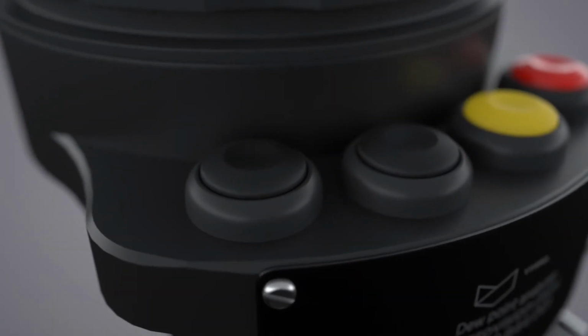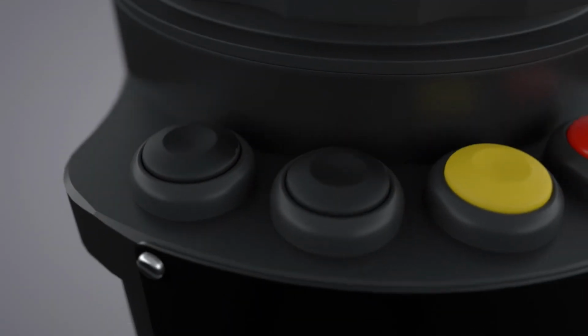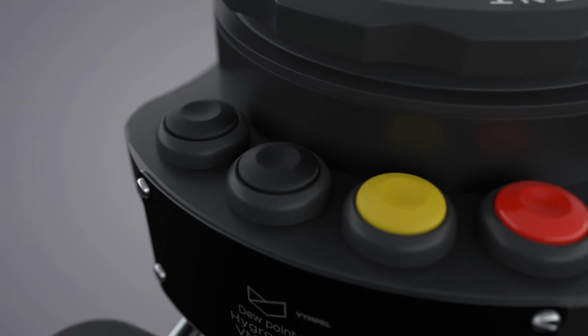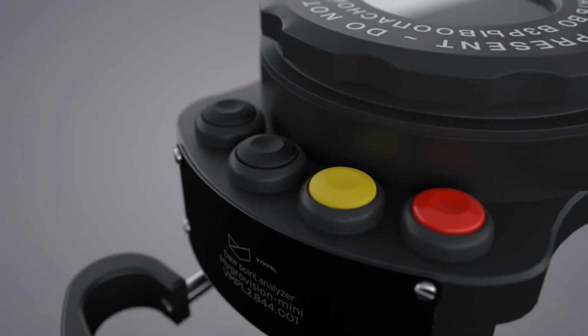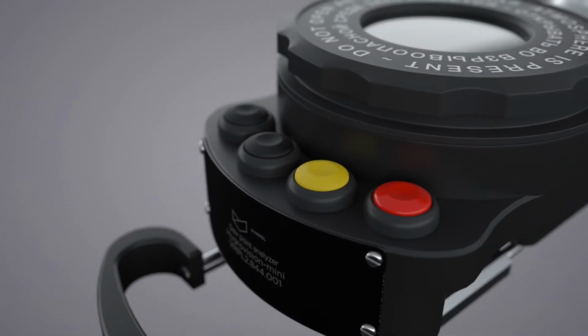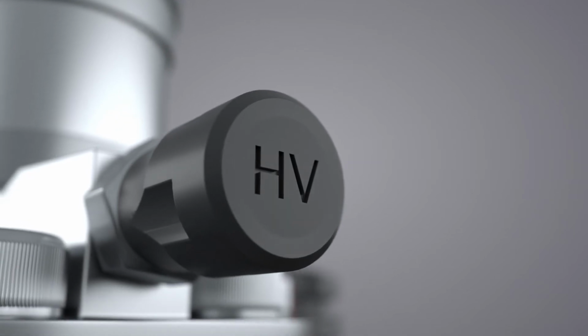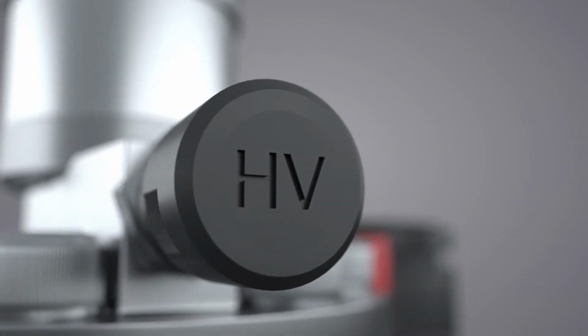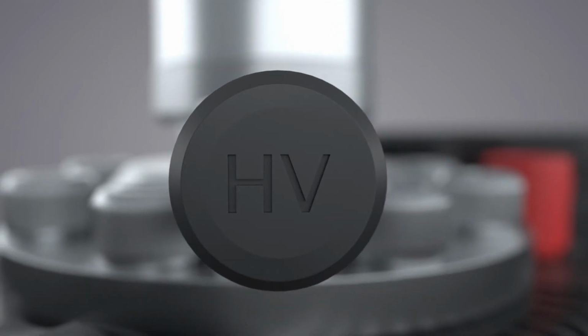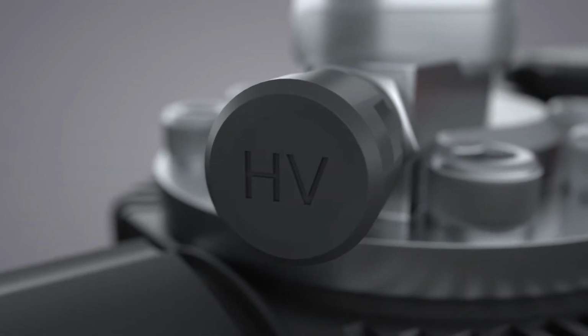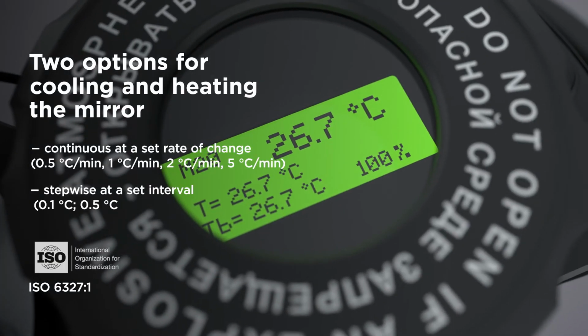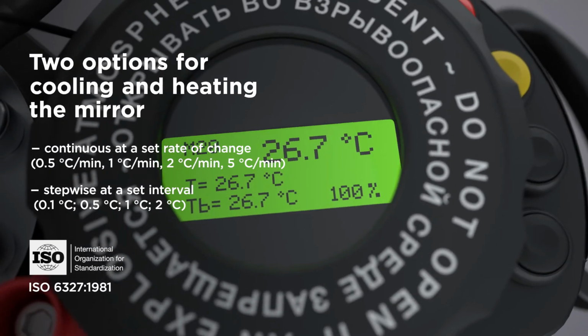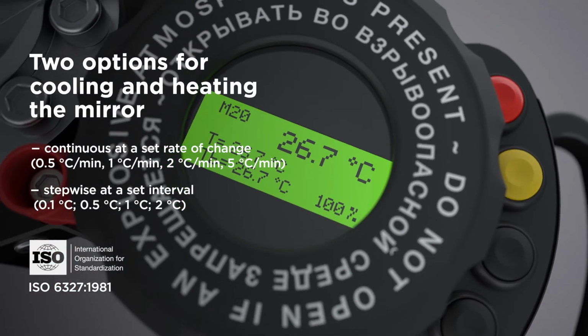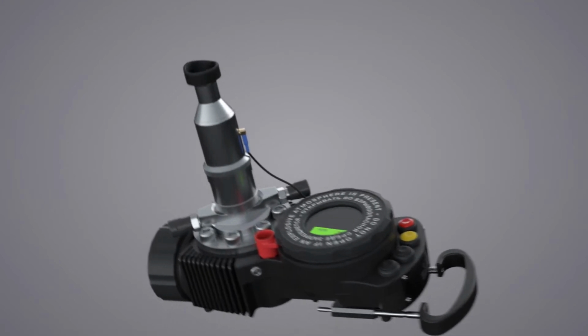The lightweight portable instrument is conveniently operated by means of a keypad and display. Heating and cooling of the mirror is accomplished by a thermoelectric battery, eliminating the need for cumbersome refrigerants. Moreover, thanks to semi-automated features, the rate of cooling and heating of the mirror can be preset, allowing the operator to use the Hygrovision-mini to make measurements in accordance with GOST or ISO standards.